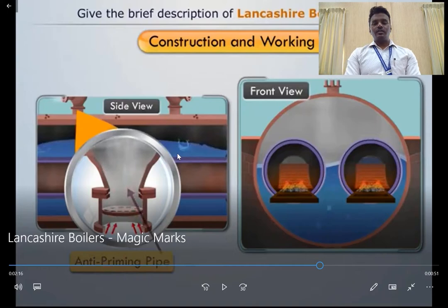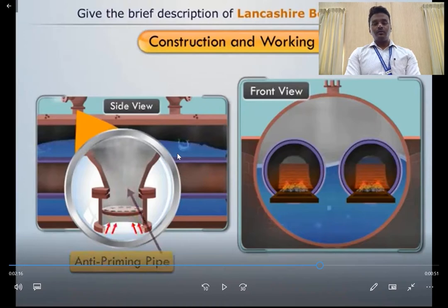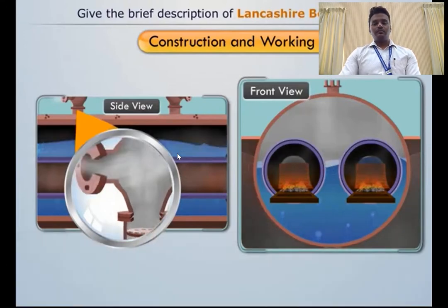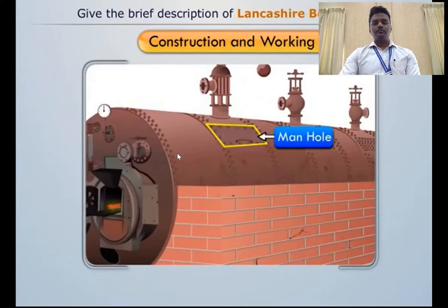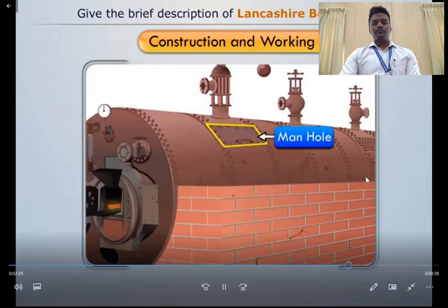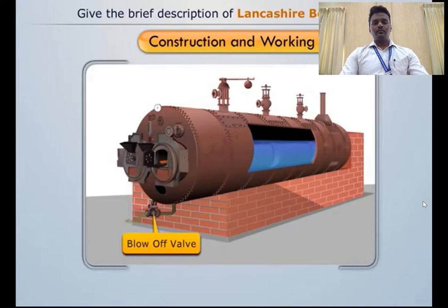Once the boiler is heated adequately, water converts into steam by absorbing heat from the flue gases. This steam is stored at the upper portion of the boiler shell, where an anti-priming pipe separates water from steam. The steam may contain water molecules — if wet steam is supplied to run a steam turbine, it creates problems like corrosion and erosion of turbine blades. To prevent entry of water molecules and supply good quality steam, we make use of an anti-priming pipe. The steam stop valve then receives the dry steam. A manhole is provided at the top and bottom of the shell for cleaning. A blow-off valve removes settled mud and empties the boiler.